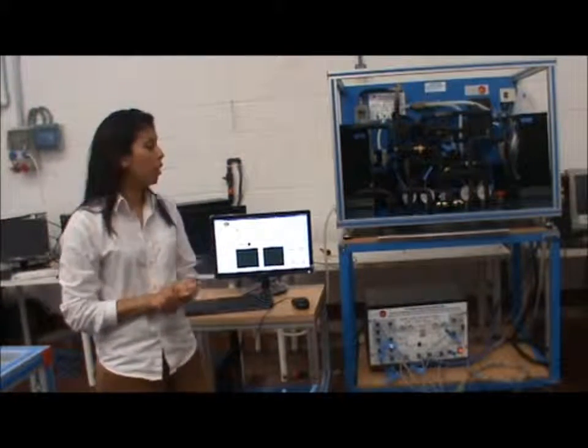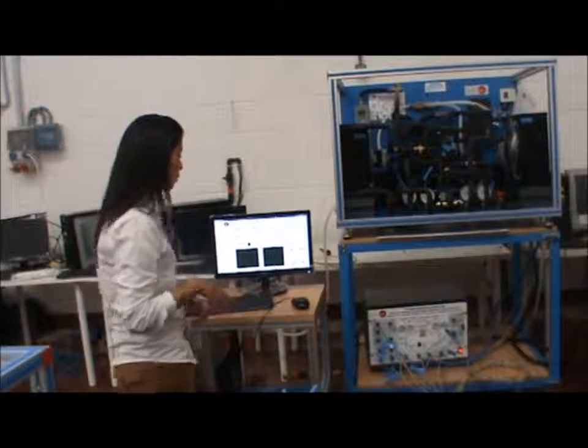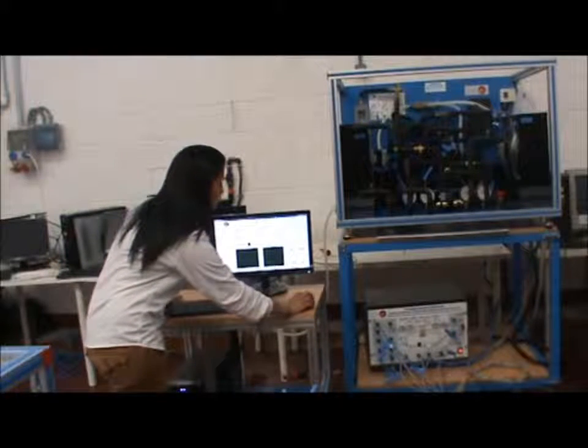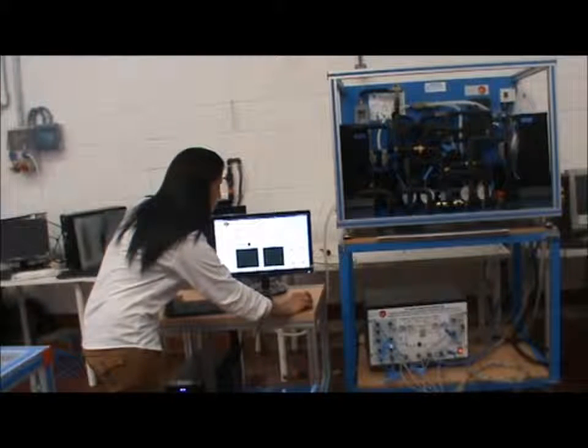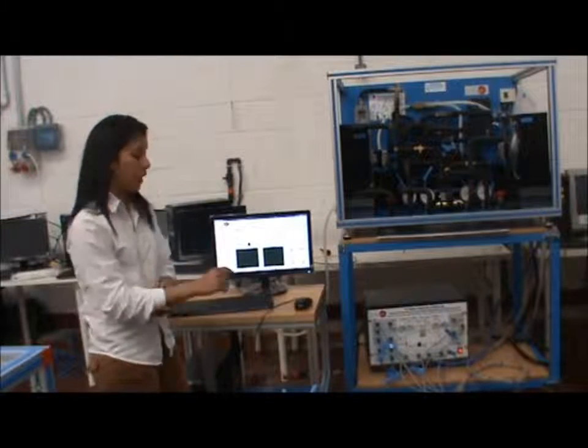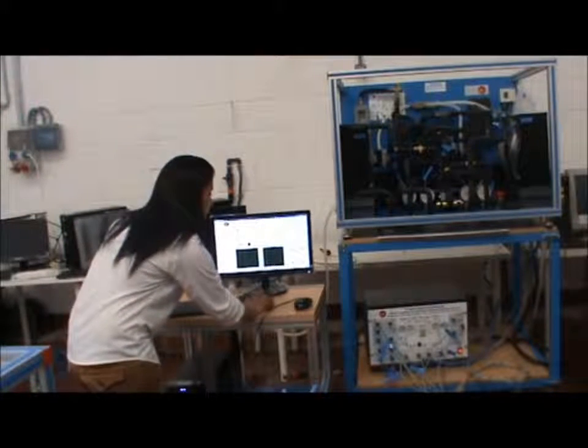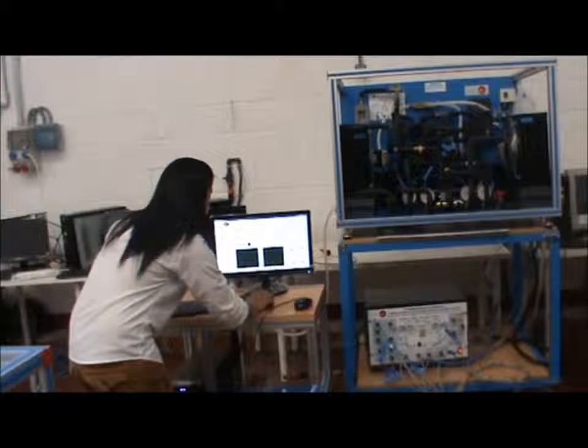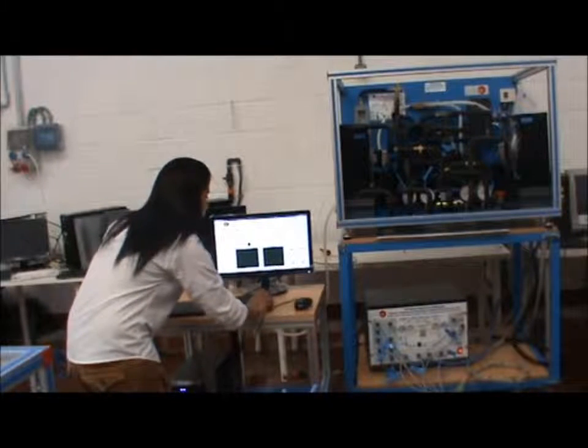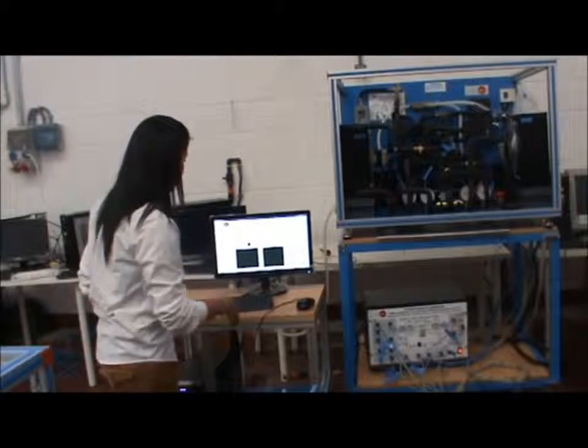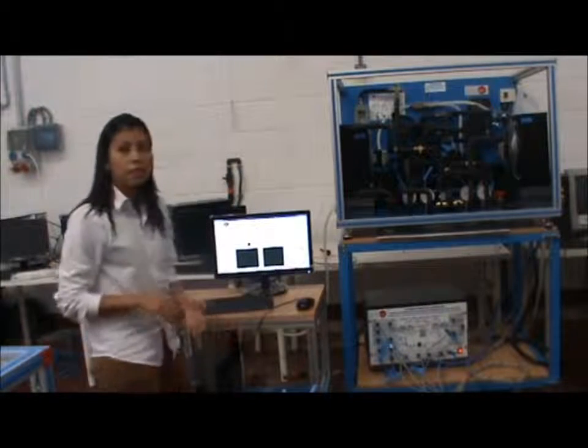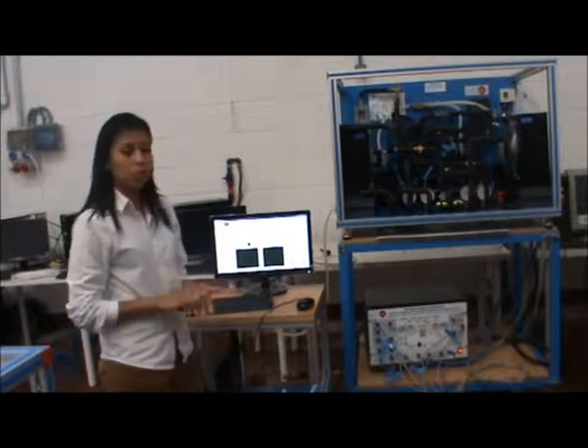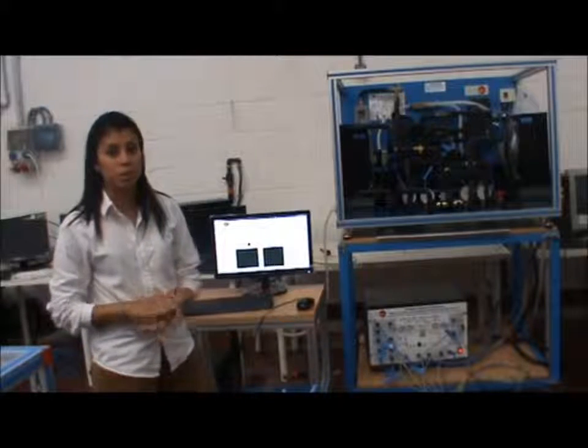Now, after you open all the valves, you have to choose the position of the equipment. It can be position 1 or position 2, depending on the process you want to perform with this equipment. We are going to choose position 1 and then choose the speed of the fans. Use 50 for both fans. Click Start, and then you will hear how the equipment starts working. It's very important to know that once you choose position 1 and press the compressor button, you won't be able to change from position 1 to 2.